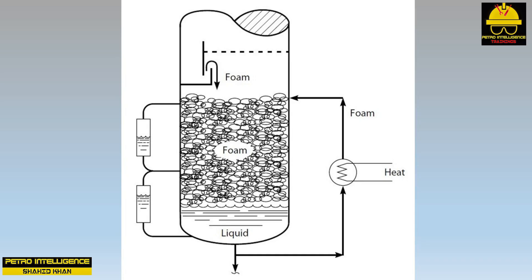Split liquid levels: the two gauge glasses shown in this picture both show a liquid level, but we cannot have alternating layers of liquid-vapor-liquid-vapor in the vessel. These split liquid levels are a positive indication of foam or froth in the bottom of the tower. If foam spans both taps on a gauge glass, the height of liquid in the glass measures the specific gravity of the foam. These split levels tell us nothing about the real liquid level — they are simply a sign of foam.